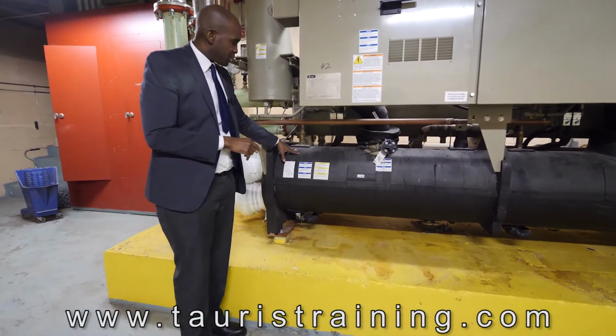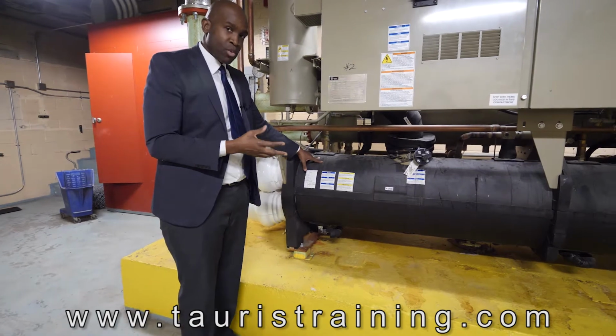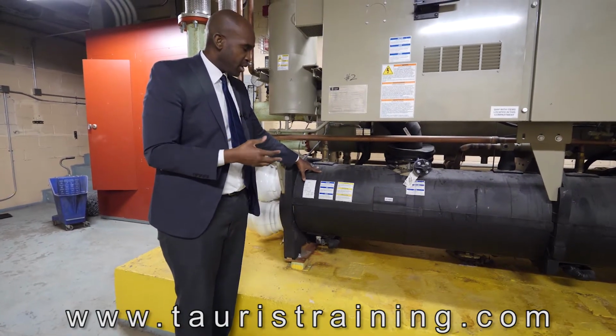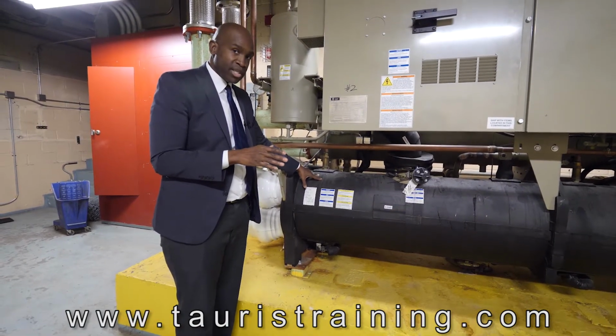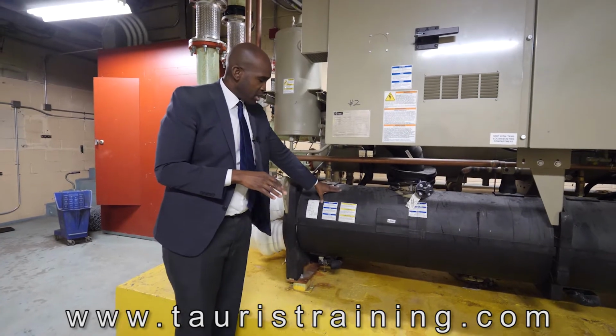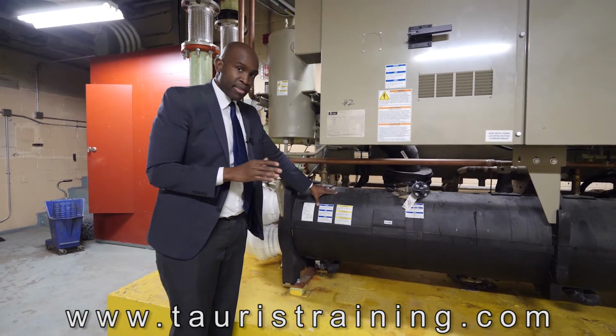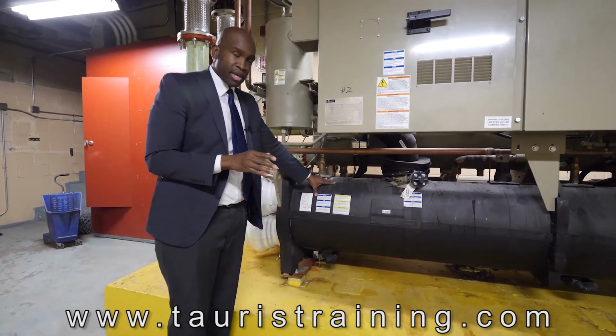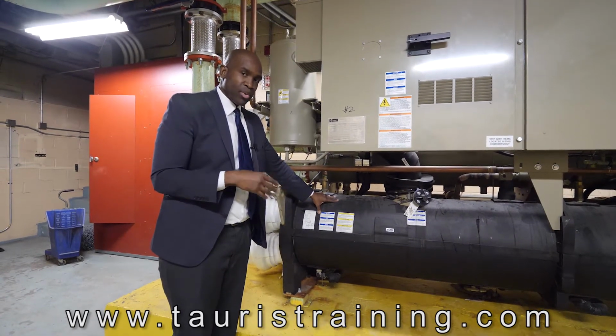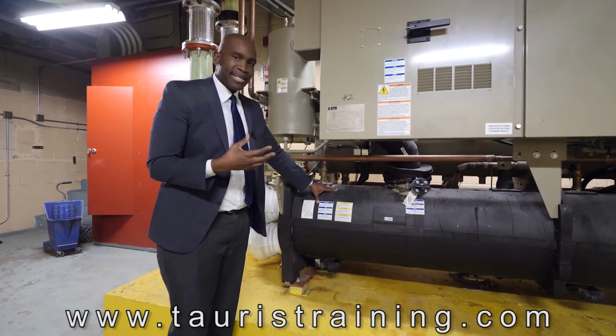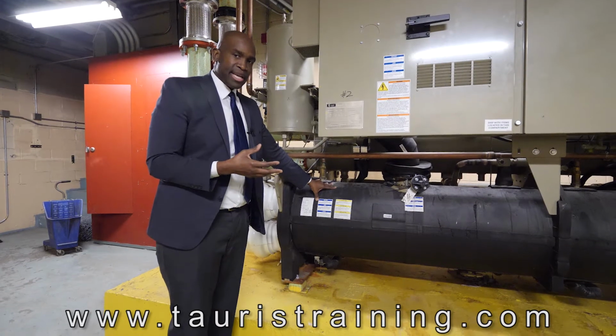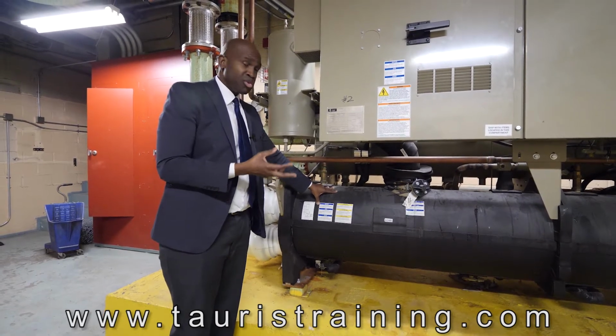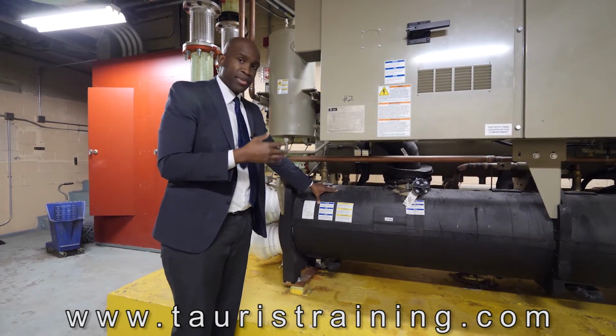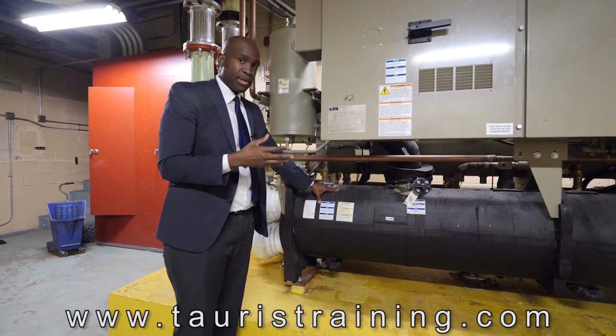So the evaporator is essentially a metal container where we have refrigerant that's going to be boiling usually about 35 degrees. And the temperature of the water going in there is going to be about 55 or 45. So whenever we're dealing with chilled water, we have the risk of condensation. Condensation is when you have essentially drops of water being condensed from the air forming on the metal piping.